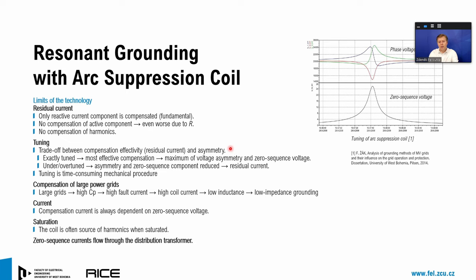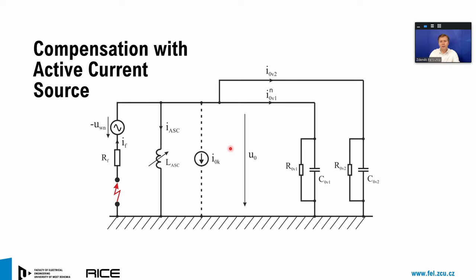So we have been thinking about how to overcome these constraints of the state-of-the-art technology, which has been operated in power grids for more than 100 years. And we came up with a power electronics based solution. We came up with the active current source, which can operate together with an arc suppression coil or fully independently of the arc suppression coil and can replace the arc suppression coil in the grid.